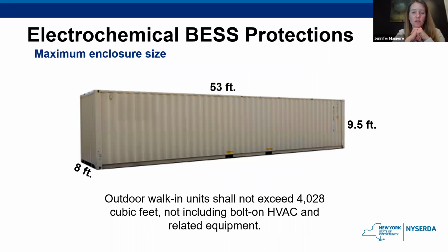There's a maximum enclosure size for outdoor walk-in units. It was originally just those dimensions that you see on the screen, 8 by 53 by 9.5 feet. That was a little restrictive in shapes. So the code requirement now is just no larger than 4,028 cubic feet. And it's not that you can't have a system that takes up more space than that. It's just that if you're going to have it all in one container, after that, it's no longer an outdoor walk-in unit. It would just be treated as a building, like any other building, once it surpasses those dimensions. Do we have any questions?